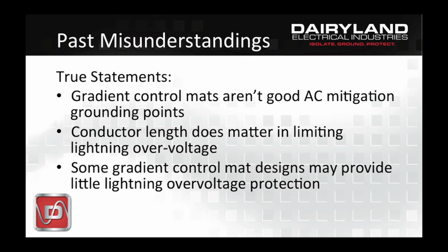Second, conductor length matters in dealing with lightning for overvoltage protection. And there's ways that one can apply and use techniques to employ limited conductor length in order to limit lightning overvoltage. Now, back to gradient control mats, not every design actually provides overvoltage protection specifically for lightning. You'd be astounded at how different the performance can be between different mats.